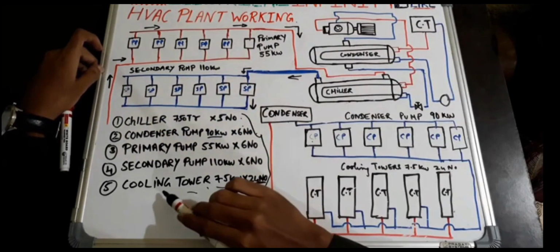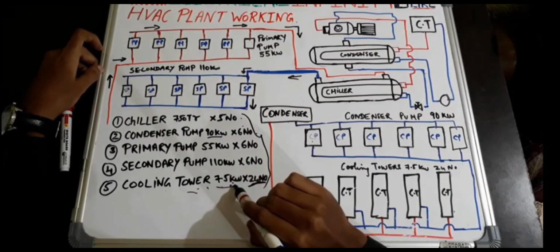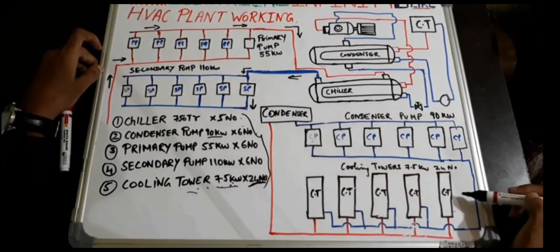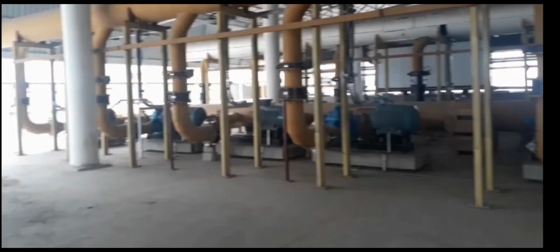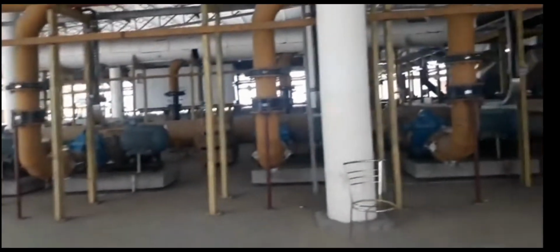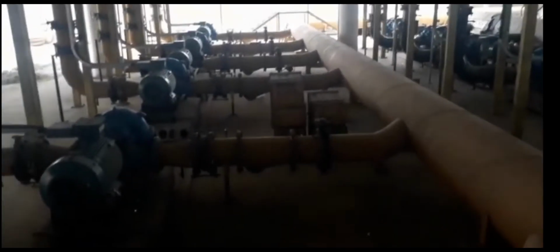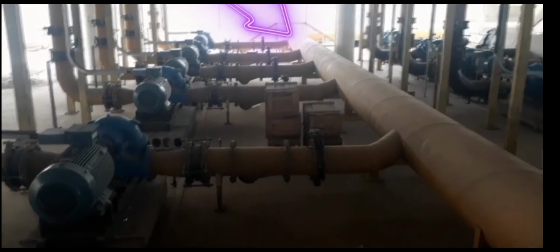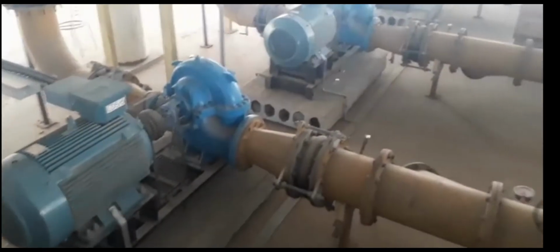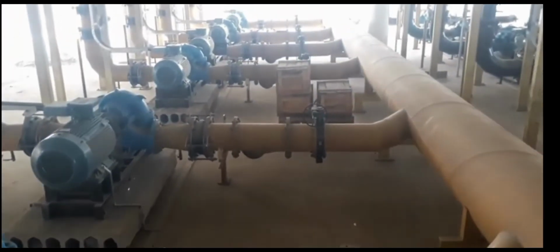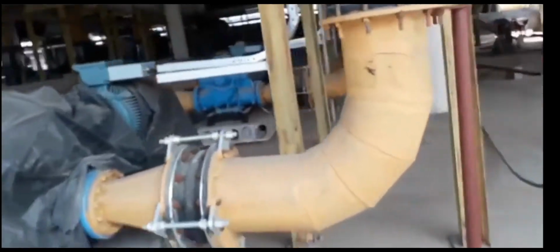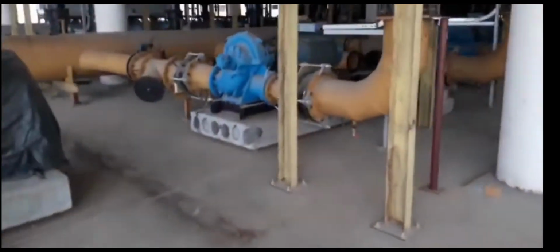Also we are using 24 cooling towers, each of 7.5 kilowatt. I have drawn only 5 cooling towers here as there was no space left. Here you can see these are the 6 condenser pumps which are used for pumping the cool water from the cooling tower to the condenser for cooling of the refrigerant of the condenser. As you can see here, this is a big yellow pipe coming from the cooling tower. This pipe carries cool water from the cooling tower, and with the help of the condenser pump, the cool water is pumped into the condenser. We have used 6 condenser pumps, each of 90 kilowatt, for pumping cool water from the cooling tower into the condenser.